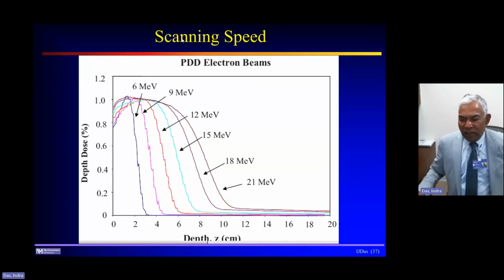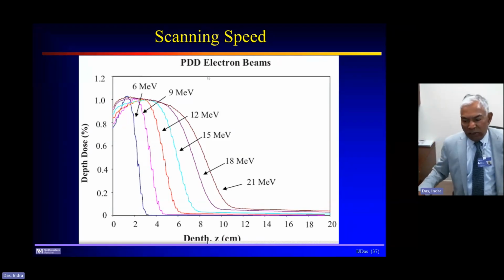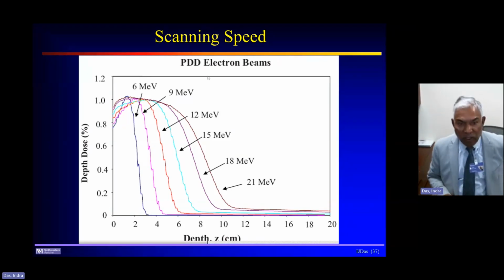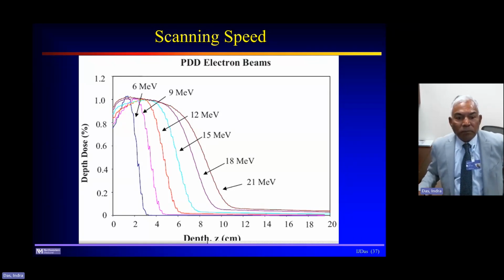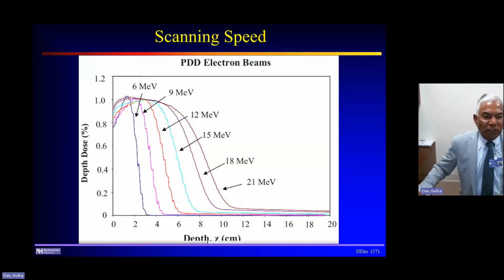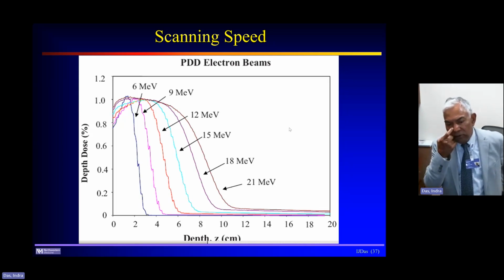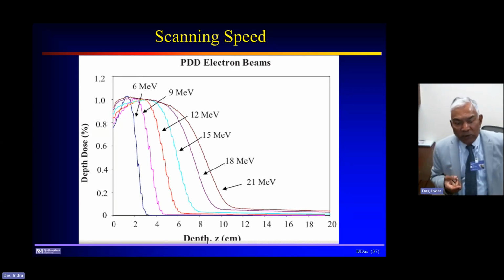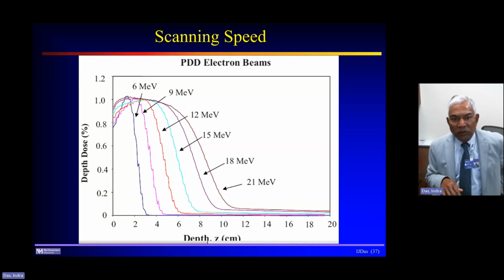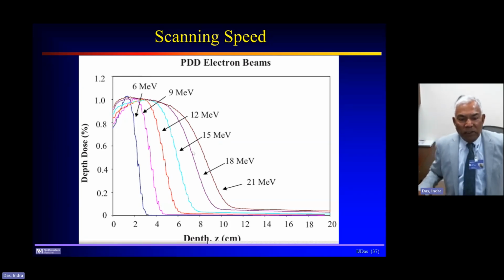Scanning speed is another issue you must pay attention to, especially for small fields. If you see your depth doses coming out jagged like this, it should immediately come to your mind that your speed is very different, because a slight change in water ripples changes the whole depth dose pattern. This is a typical diagnosis for electron beams and all that. So those are the things that you need to think about.